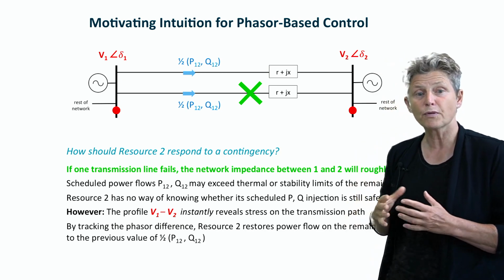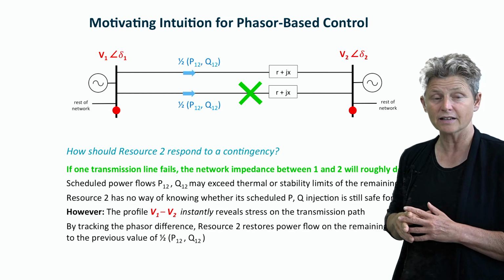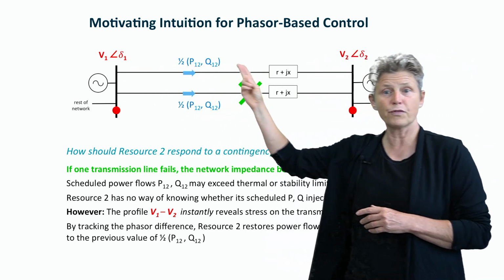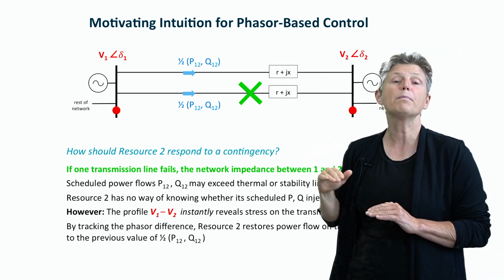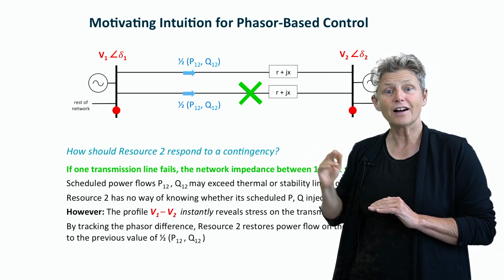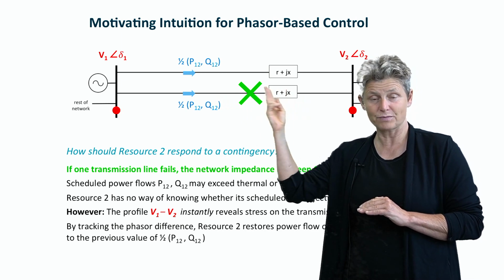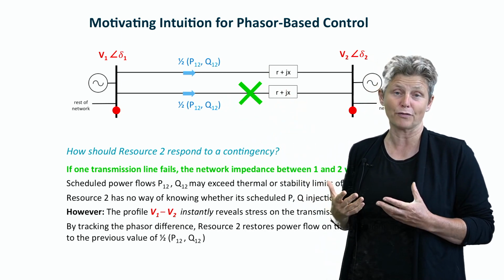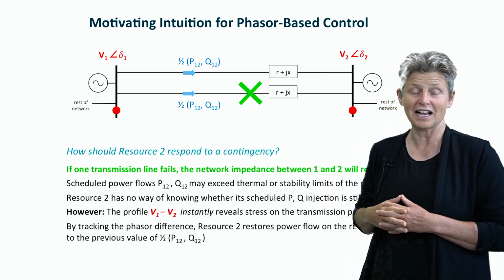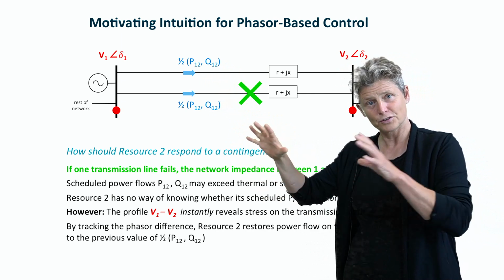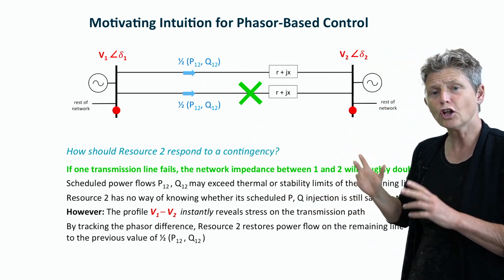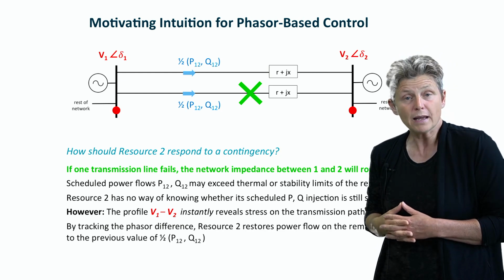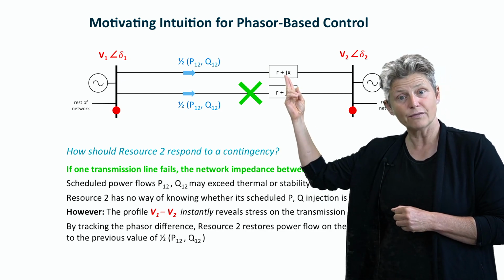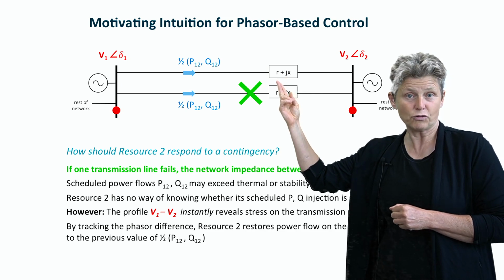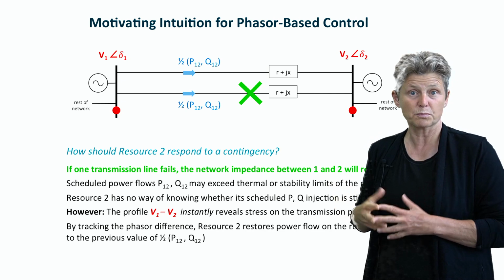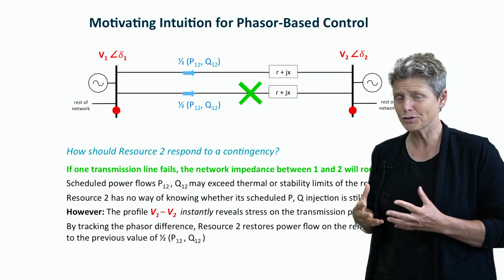The consequence, before any other control actions have been taken, is that this phasor difference, V1 minus V2, will jump up instantaneously because there is now a bigger impedance, and there will be an attempt to transfer the same amount of power. It won't actually come out to be exactly the same amount because some of it will rearrange itself in the network.